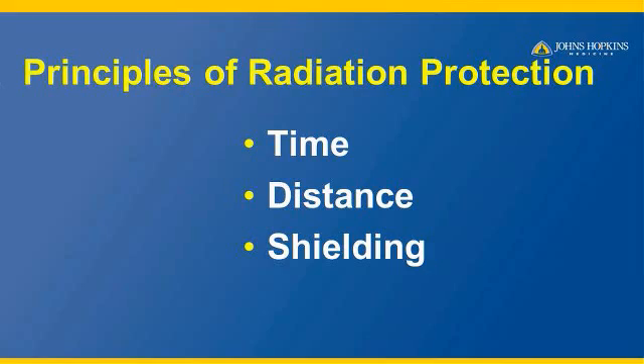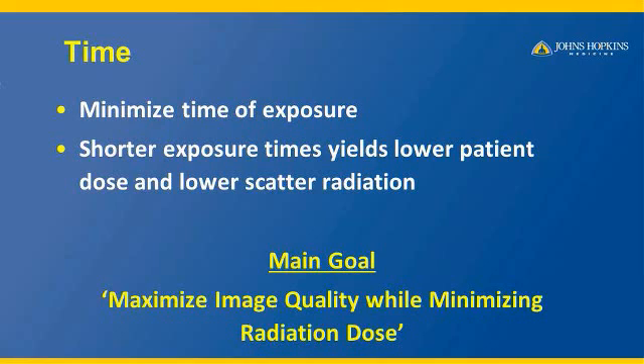When you say radiation protection, the three pillars of radiation protection are time, distance, and shielding. These three pillars provide the realm of understanding for radiation protection. When you say time, the time it takes for exposure results in the radiation dose to the patient and also yields scattered radiation coming out of the patient. Therefore, if you minimize the time of exposure, that will yield lower patient dose and also lower scattered radiation.